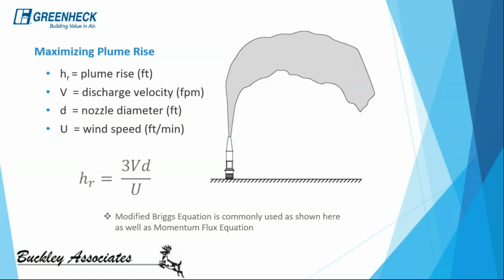There are many variables that play into this entire design, including the airflow, the discharge velocity, the actual nozzle diameter of the fan. Some of these fans can come with a variable nozzle, so we can continuously maintain a maximum plume rise and even a constant discharge velocity here. And we'll talk about that a little bit more on the next few slides. But nonetheless, that variable nozzle is an option. But we need to pay attention to all of these variables.